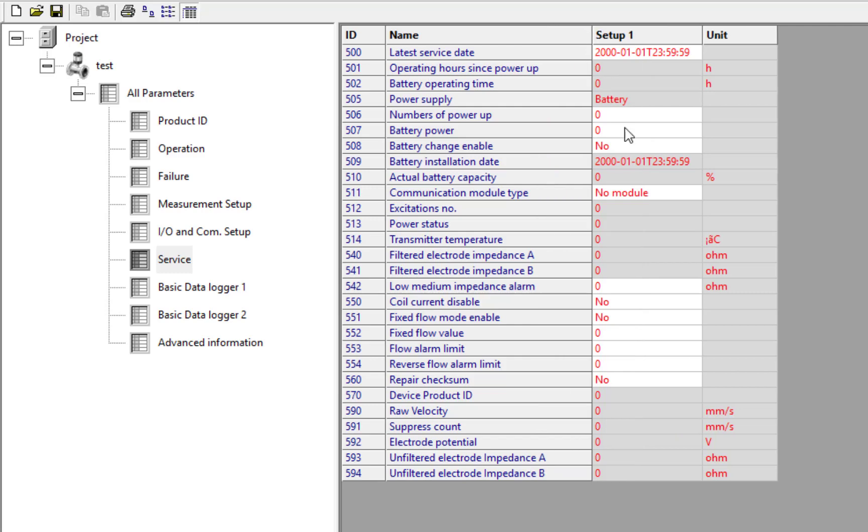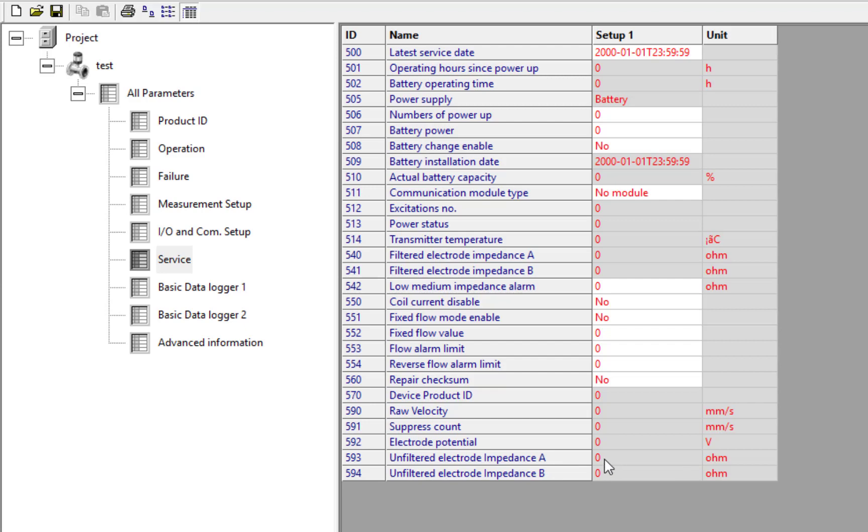We mentioned the electrode impedance. Before, we had the filtered electrode impedance. Well, now there's an unfiltered version, which is quite handy to see the raw value and to see how well the MAG8000 is filtering it or not filtering it.